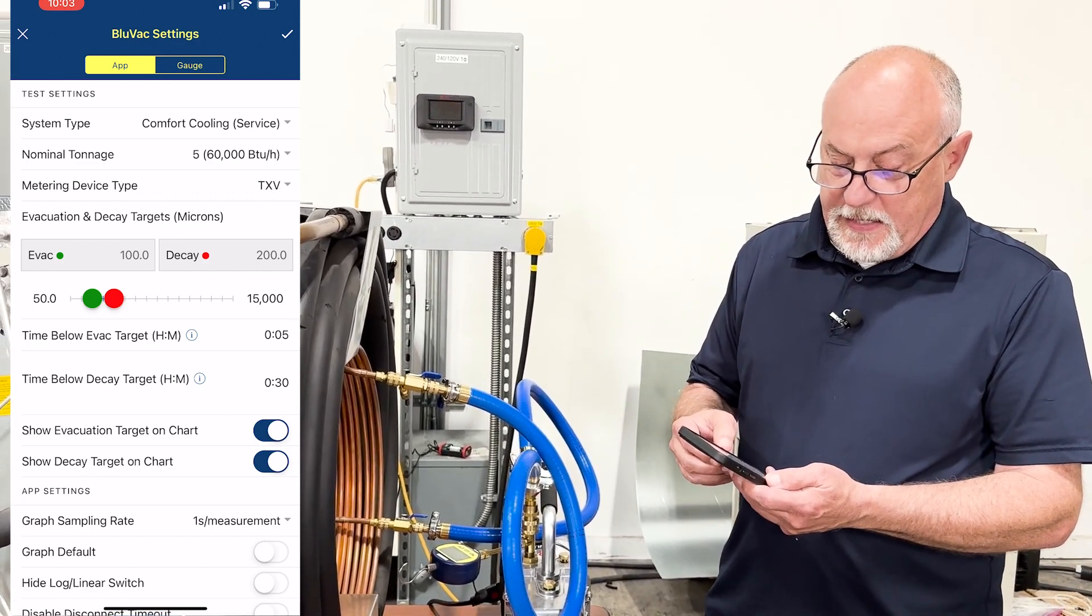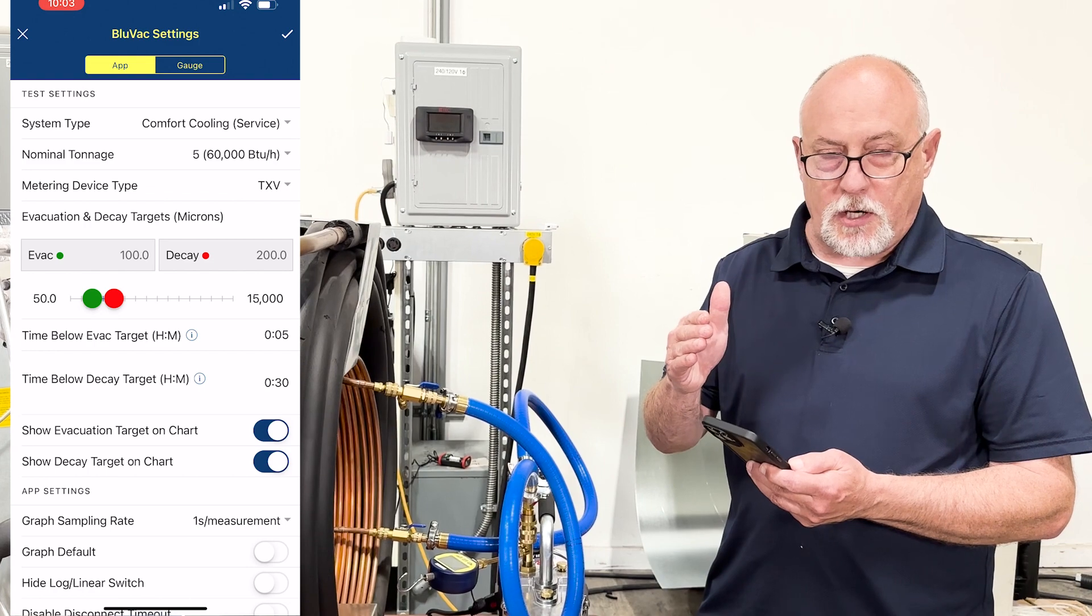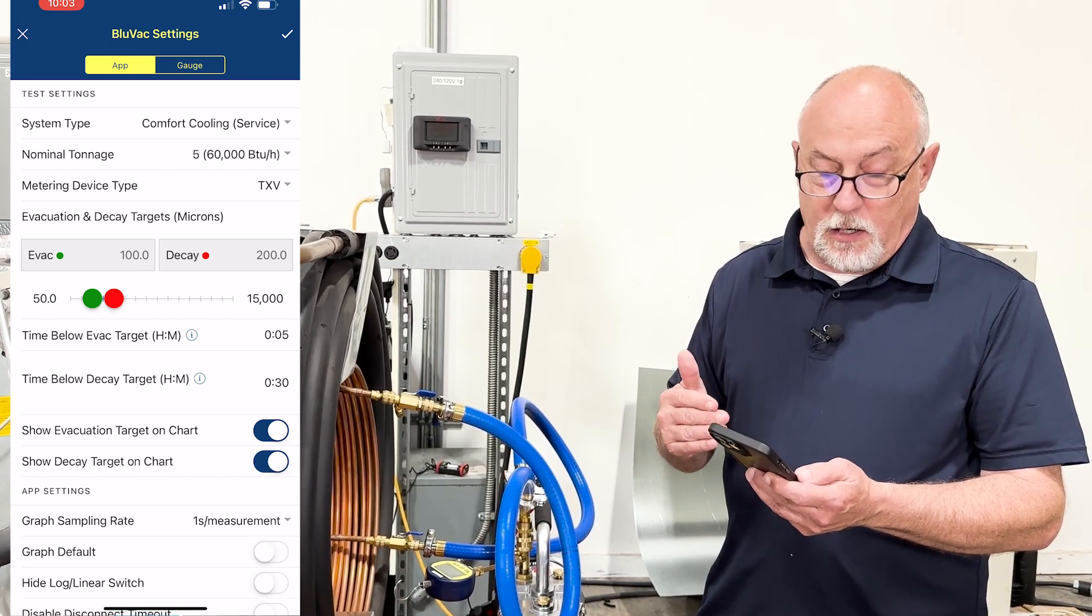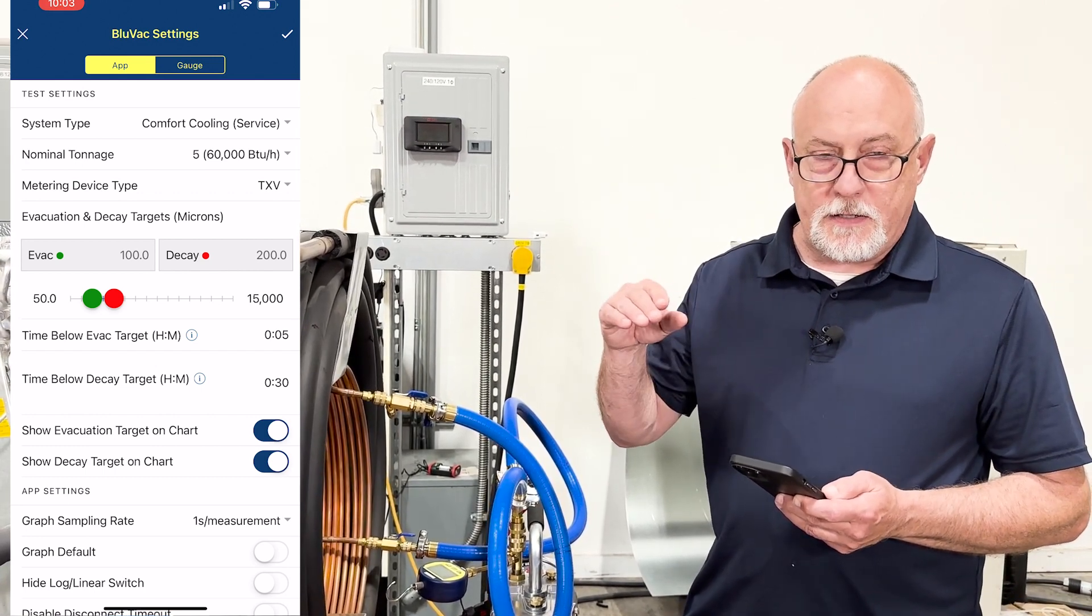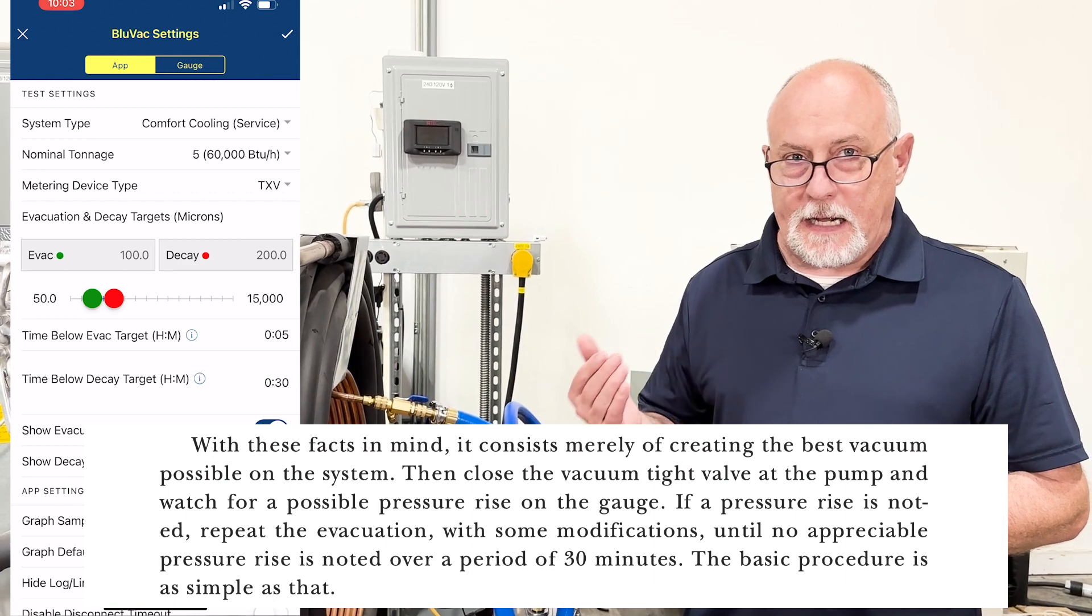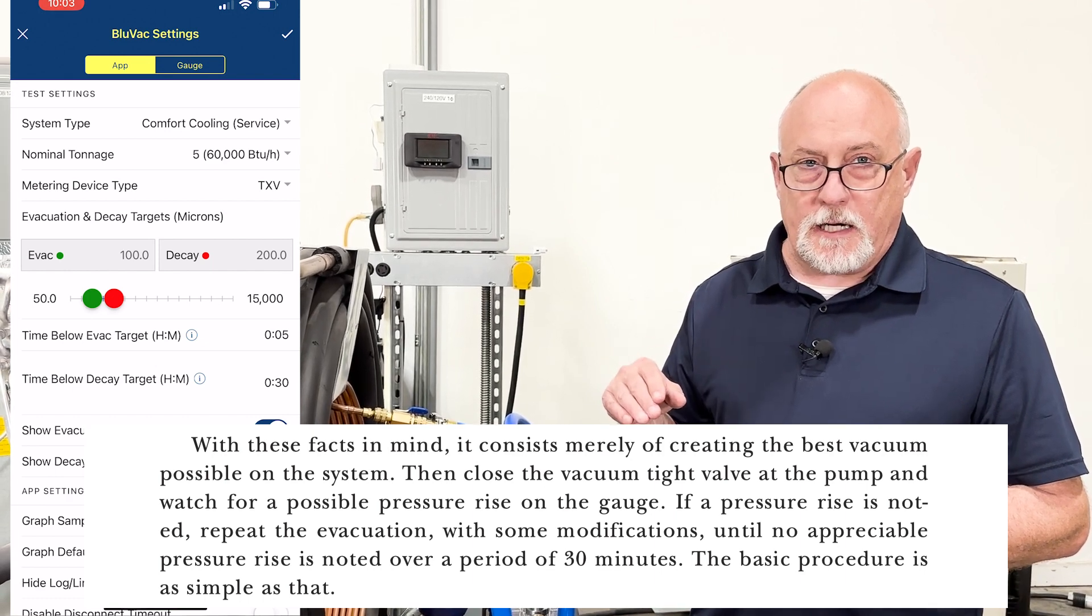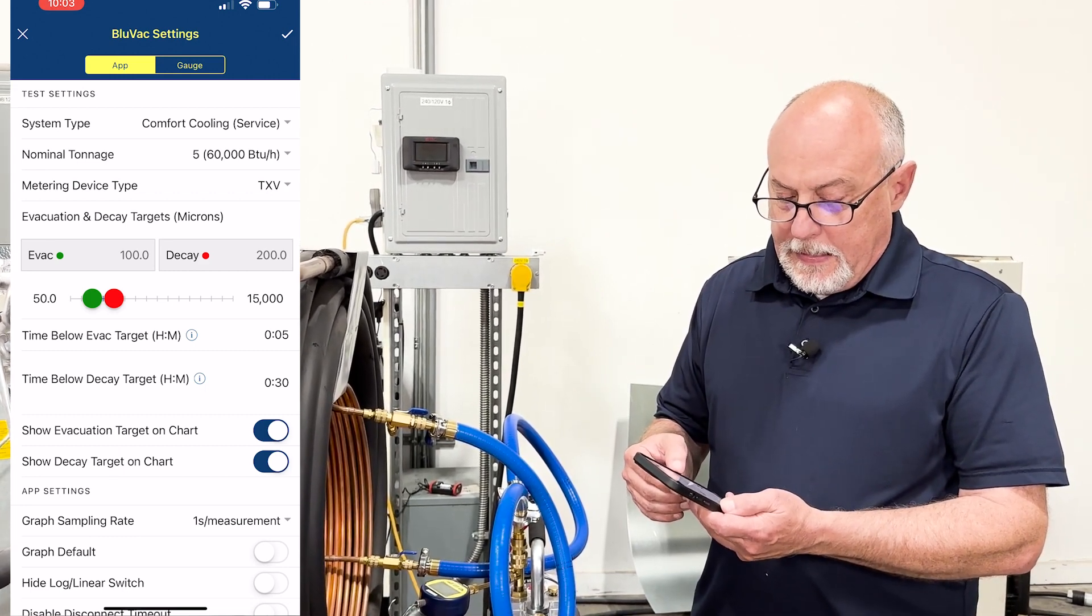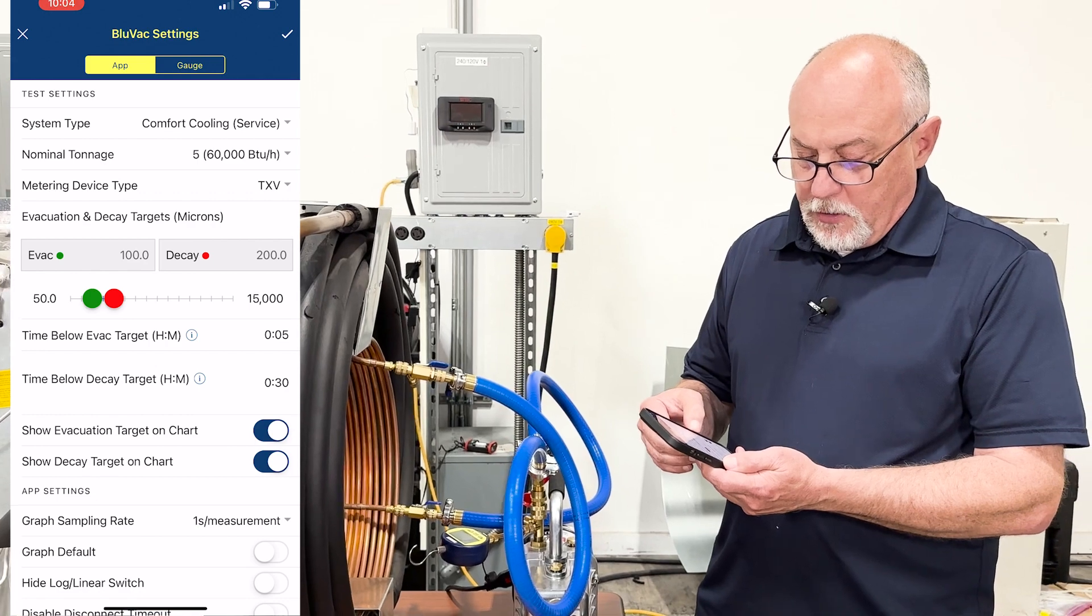Now there's a time below target setting which I have set at five minutes. So that means when the graph as it's plotting down hits the 100 micron target, we're going to hold below that for five minutes and pull down below 100 microns. And then I have my time below decay target or my decay time set for 30 minutes. Now what we wanted to do with this is make sure that there's no appreciable rise after 30 minutes. Back in the day we'd actually have to wait 30 minutes, and the BluVac app has an algorithm in it that actually watches the rise over run and can tell you in about 30 seconds to a minute if you're going to pass that 30 minute decay test.